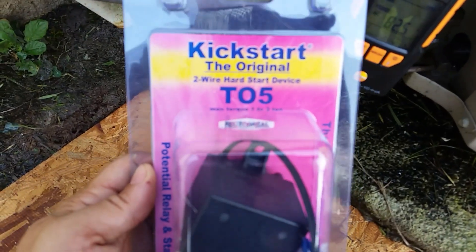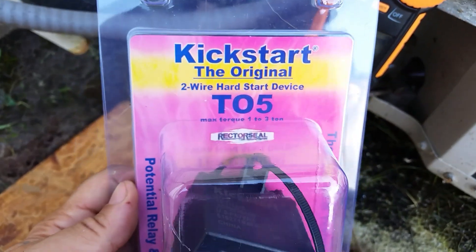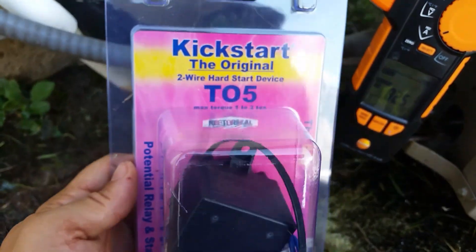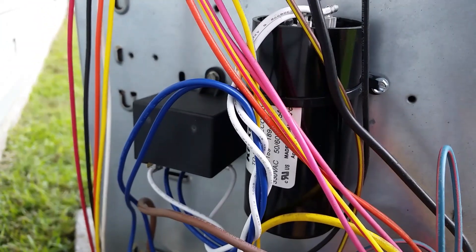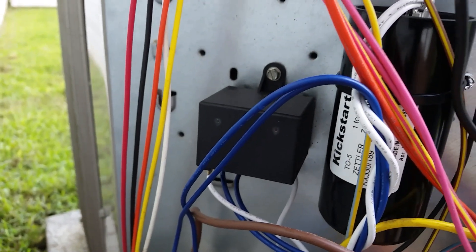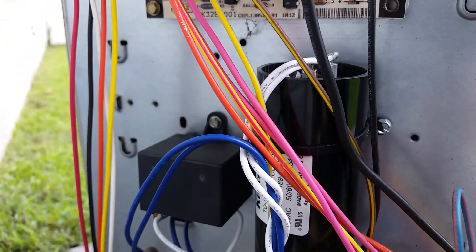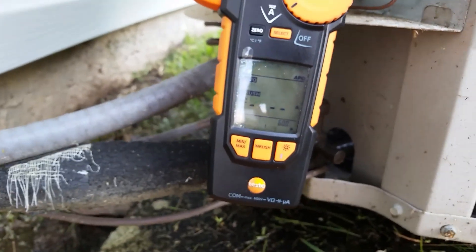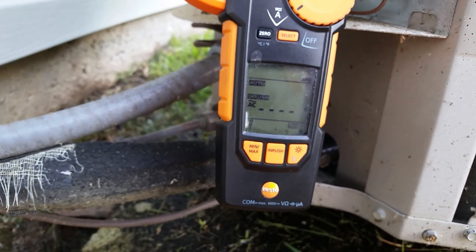I'll go ahead and shut her down. Now we are going to install our Kickstart by RectorSeal. This one is good for one to three tons — this unit being a two and a half ton should be perfect. We'll go ahead and get her installed and see what she does with the Kickstart. We got our Kickstart mounted and ready to go. Comes with basically all your mounting hardware aside from two screws. Very easy to install, very quick — just a two wire setup. Everything else is already factory wired. Got our Testo 770-3 set on inrush again.